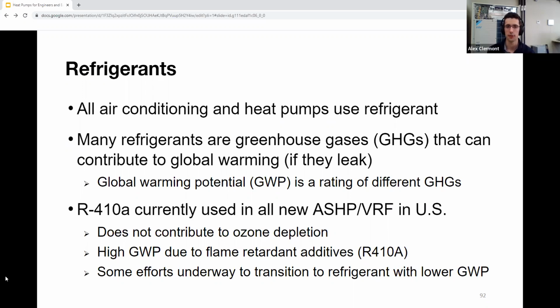Now, let's go back to R410A for a little bit. The refrigerant itself is not bad, but it's the flame retardant additive that's added to the refrigerant, which can make it have a high GWP. And there are efforts to transition to lower GWP refrigerants, which we're going to talk about now.